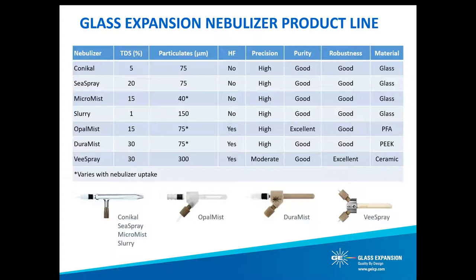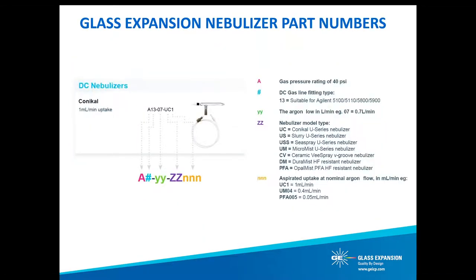The trade-off with nebulization efficiency is that the cross-flow and v-groove designs will provide a greater tolerance to particulates. Incomplete sample digestion can result in remaining particulates in the samples, which can then block the smaller capillary and gas annulus of the concentric nebulizer. The raw material of a nebulizer will also have an effect on its purity as well as its chemical resistance. Before we review each Glass Expansion nebulizer model, it's important that we understand our nebulizer part numbers as they provide critical nebulizer parameters.